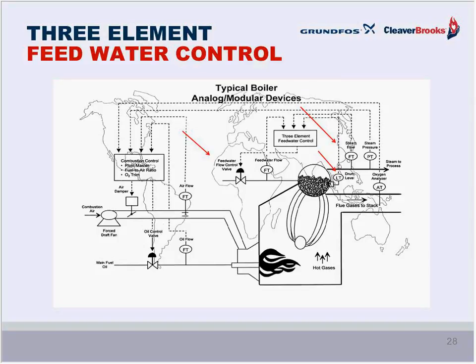Looking at the diagram on the screen now, you see the red arrows pointing to the respective elements. The level control is normally a standard level control with a loop controller indicating the level in the steam drum. And then you have another loop controller receiving a signal from a pressure transducer, or it could be a flow transmitter mounted in the header, similar to what I showed you earlier in that piping diagram.